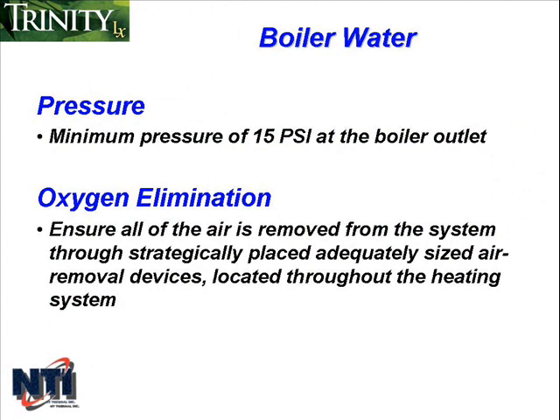Hot water boilers such as the Trinity Lx are designed to operate with airless water in the system, so an air elimination device of some sort needs to be installed in the system to remove air from the water as it circulates through. It's recommended to include an air eliminator on the secondary system as well.